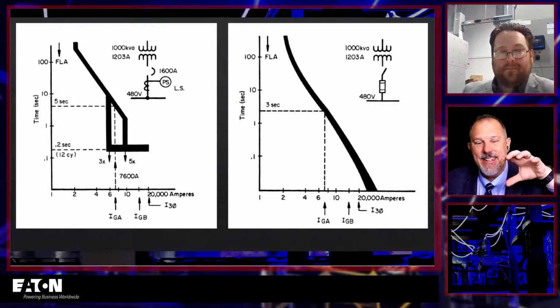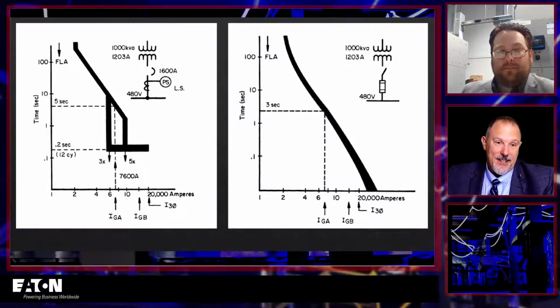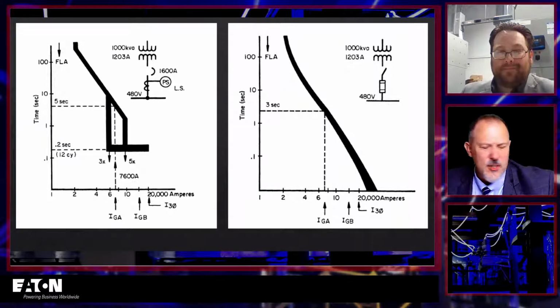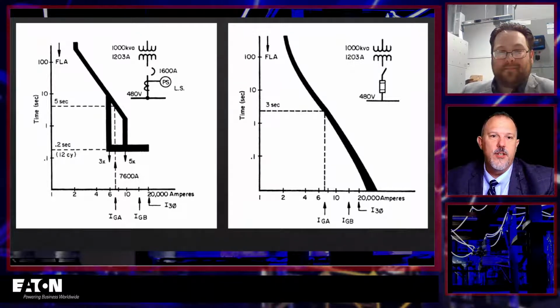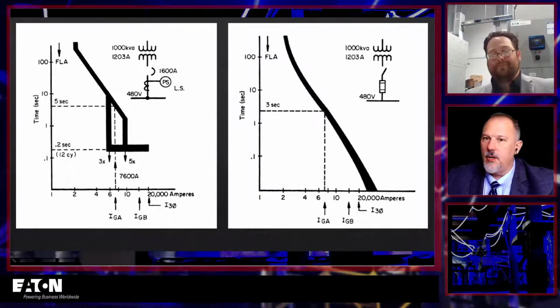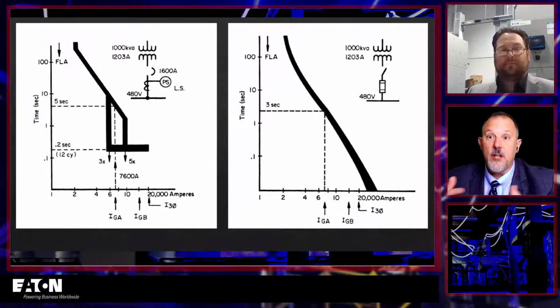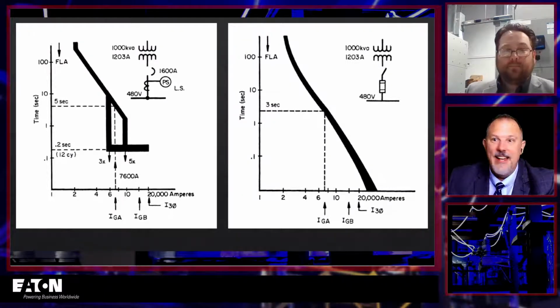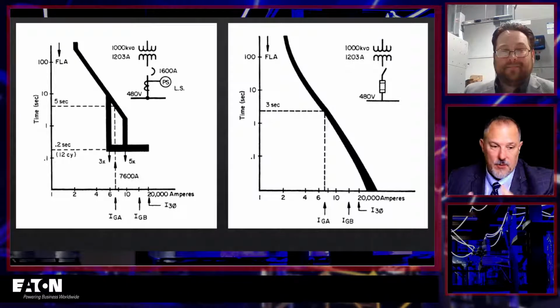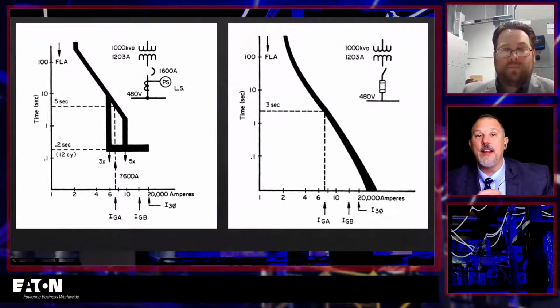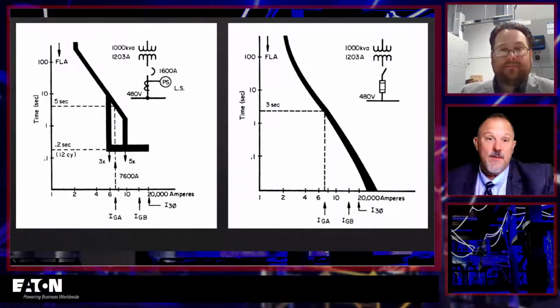And think about the history of electronics. When you're getting into the 70s, our engineers at Westinghouse were hard at work coming up with ways to address this problem, because those thermomagnetic breakers, those power breakers, weren't going to be able to do that, because why? I needed those intentional delays, because I'm serving all those loads. And they came up with the electronics as a ground fault detection device to let us dial it down for these ground fault currents.